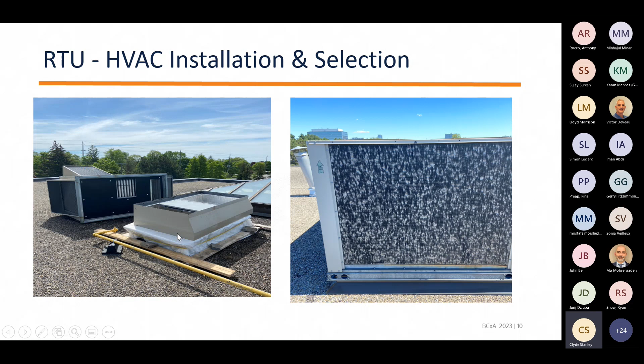When you got a lot of RTUs, you really got to pay attention, because they're getting complicated, there's a lot to them. Not everybody necessarily understands, but we got a situation here where digital compressors are cycling off at high intervals, and consuming a lot of energy. It also puts them into a situation where they're overheating, and the internal cooling and loss of oil is impacted by high cycling on and off. So that's something that's quite concerning, got to watch out for.